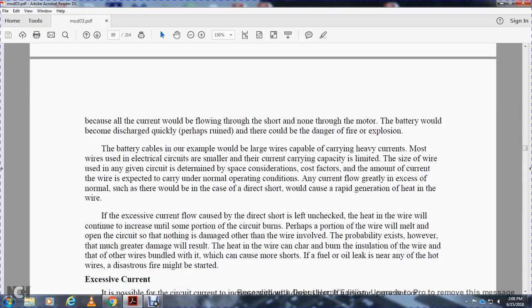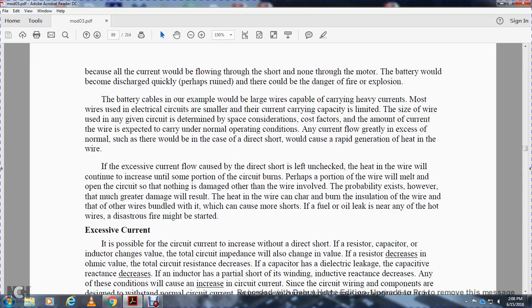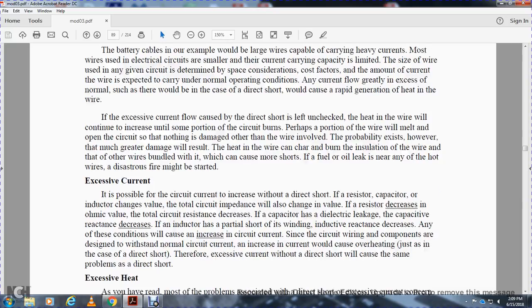The battery cables in our example would be large wire cables carrying heavy currents. Wires must be sized for the electrical circuit. Small but higher current-carrying capacity is limited by the size of the wire used in a given circuit. Design considerations factor in the amount of current the wire is expected to carry under normal operating conditions. Current flow greater in excess of the normal would be the case in a direct short, and would cause rapid generation of heat in the wire. If the excess current flow from a direct short is left unchecked, the heat in the wire would continue to increase until some portion of the circuit burns out. Perhaps a portion of the wire will melt, opening the circuit. The probability exists, however, that much greater damage will result. Heat in the wire can char and burn insulation on the wire and other wires bundled with it, which can cause more shorts. And fuel or oil leaks near any of the hot wires could start a fire.